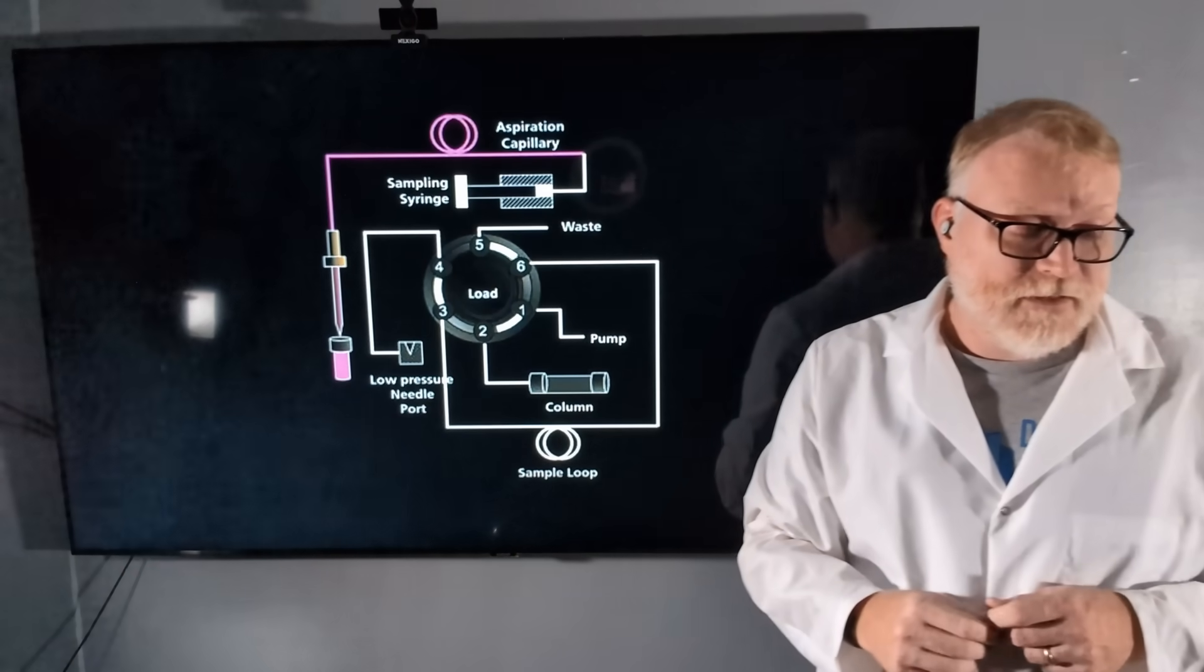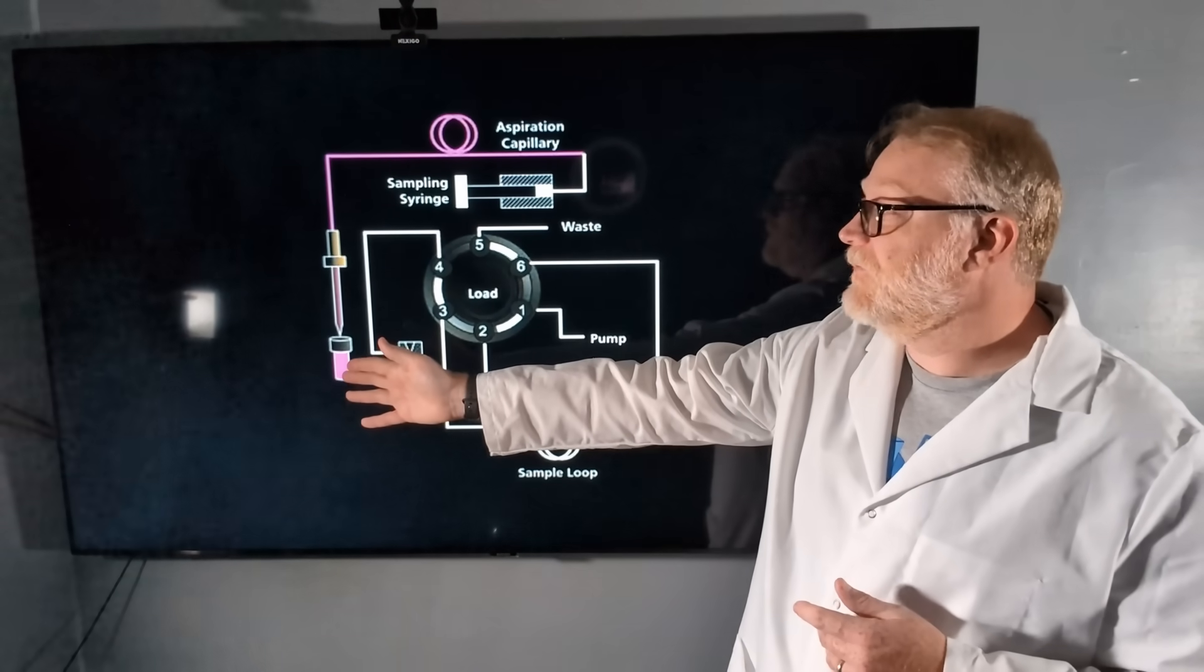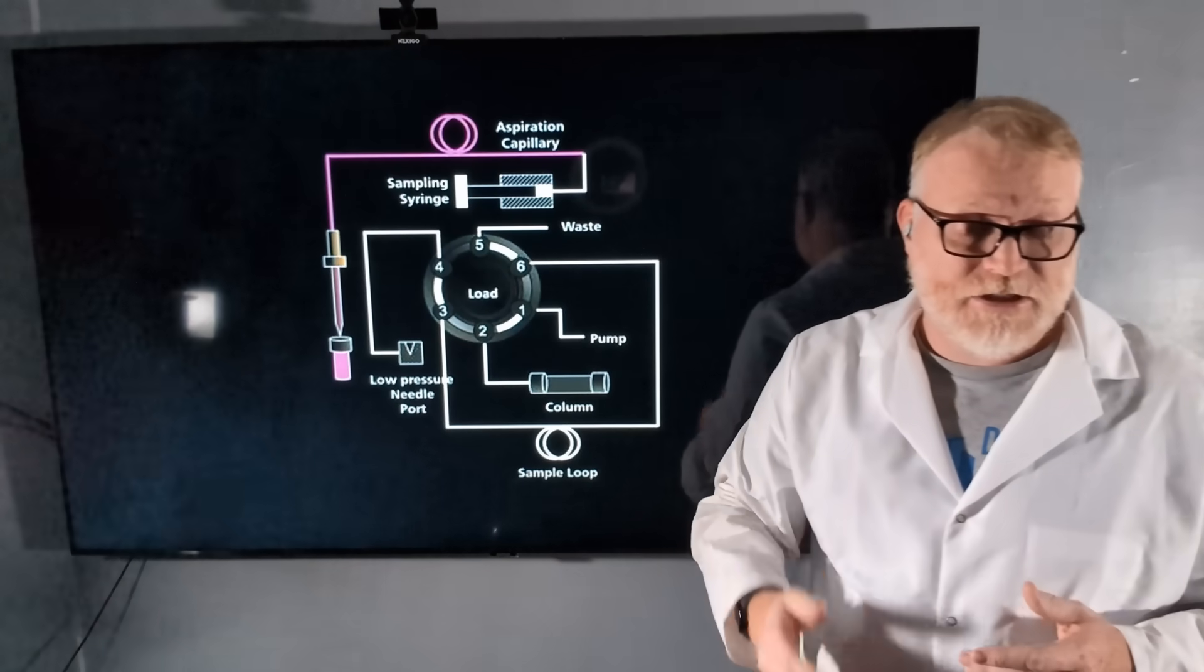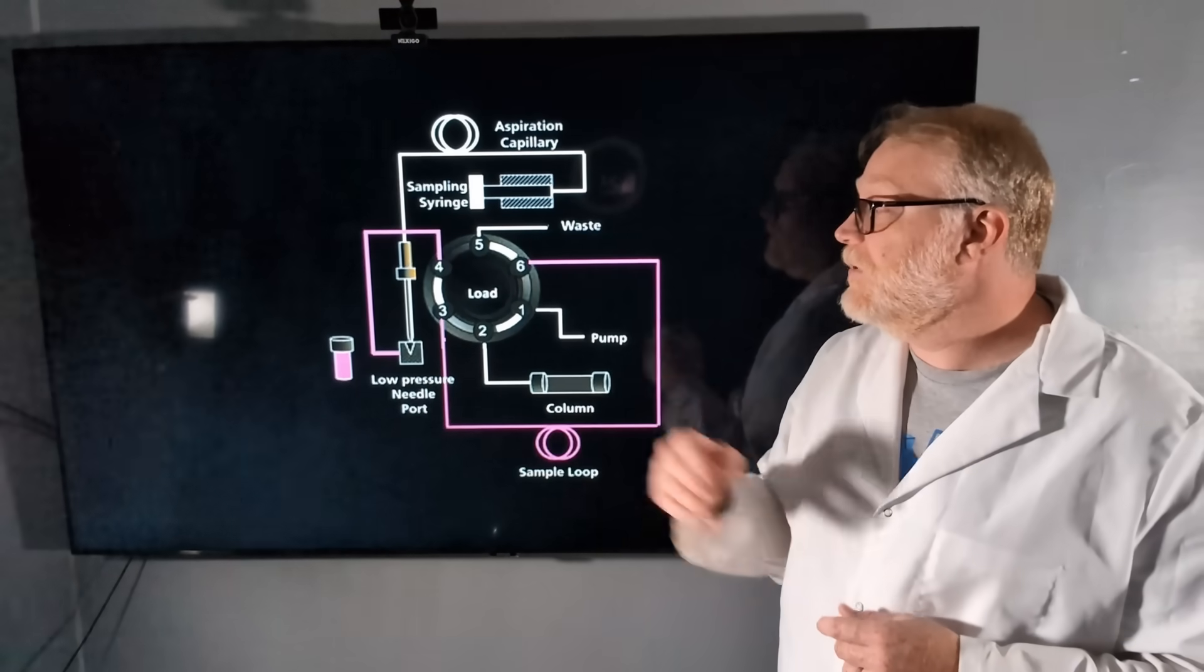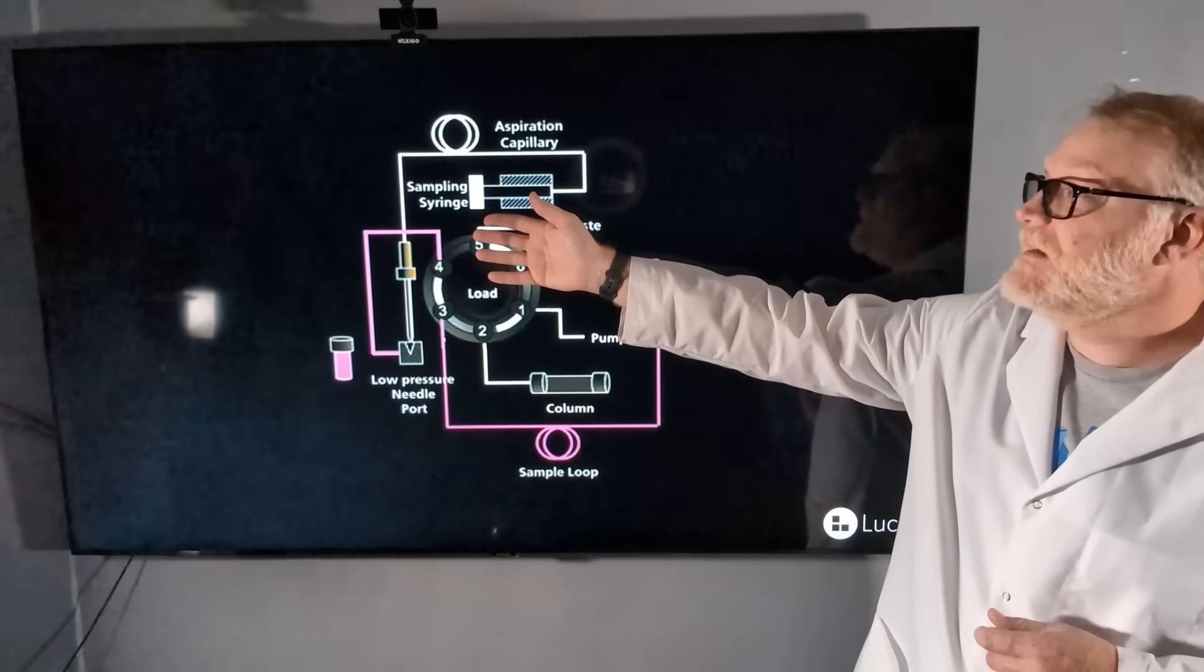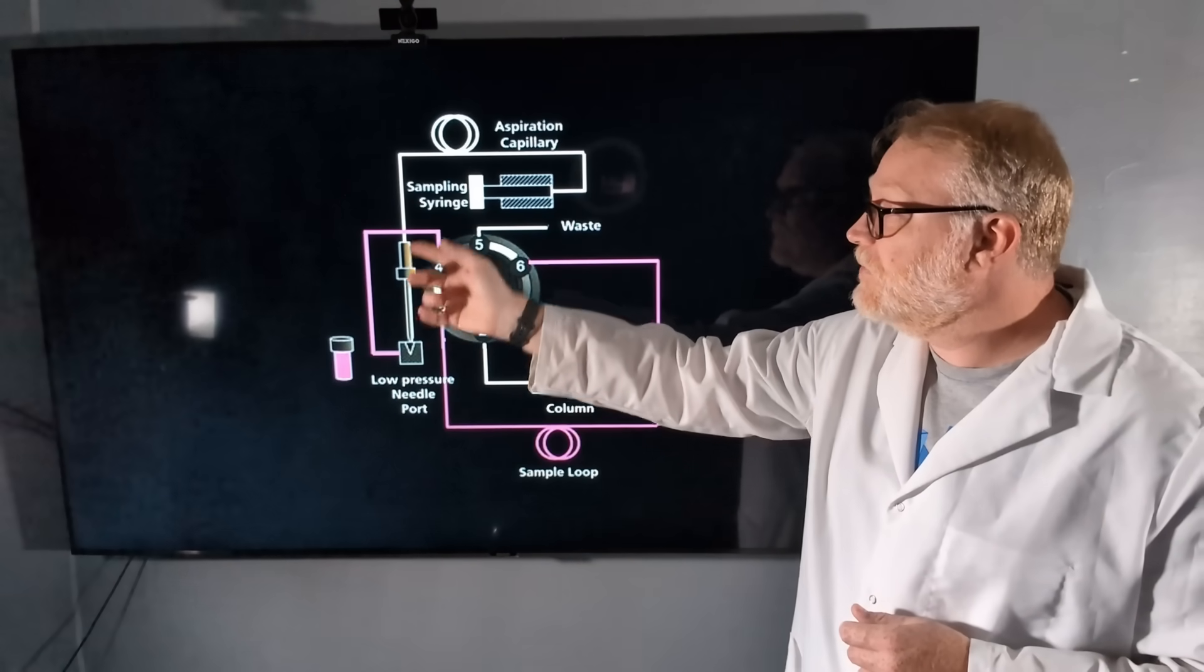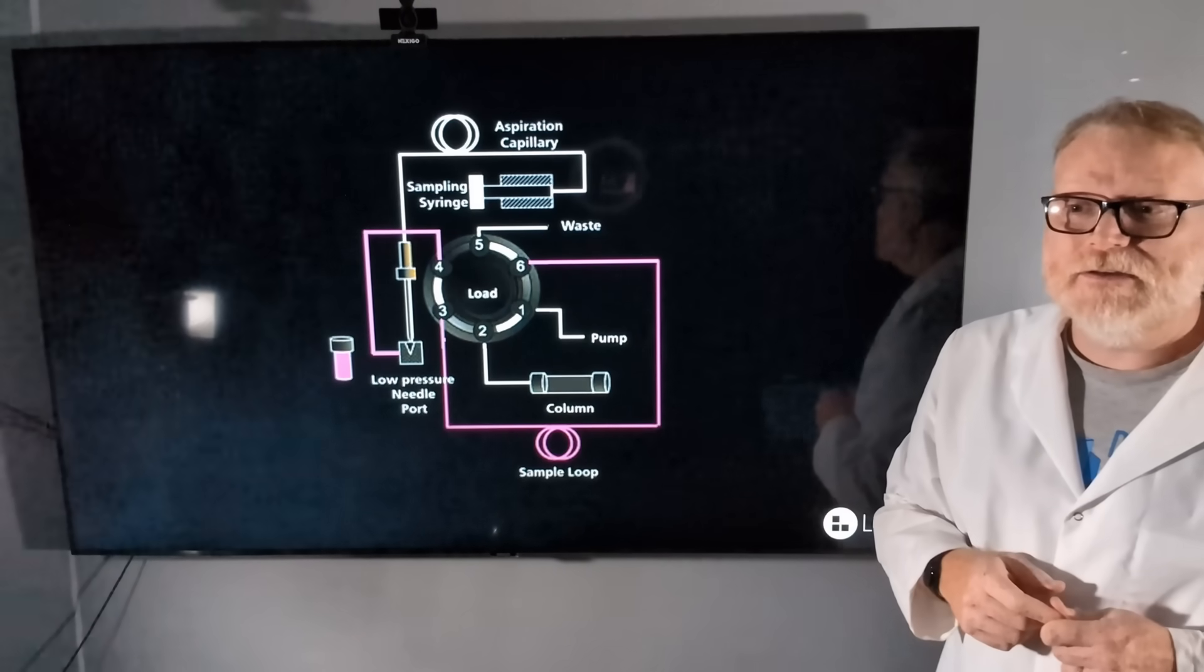When we start this up and we're pulling our sample, we're going to pull our sample from the vial into the aspiration capillary using our sampling syringe. Then we're going to move that needle into our low-pressure needle port using that same sampling syringe. We're going to push through the aspiration capillary, through our injection valve, into our sample loop.